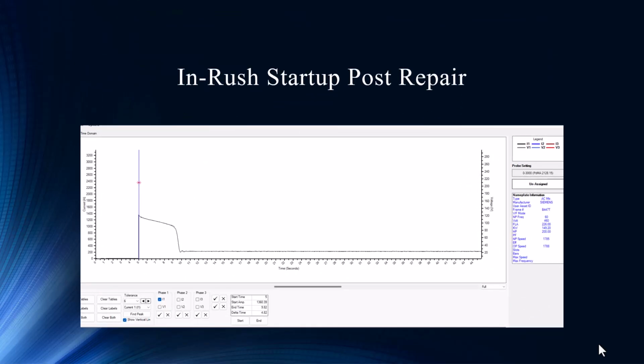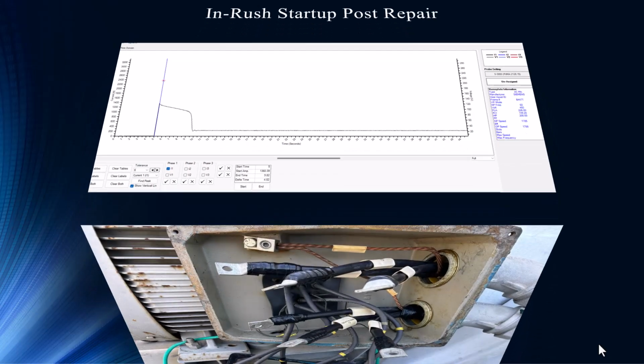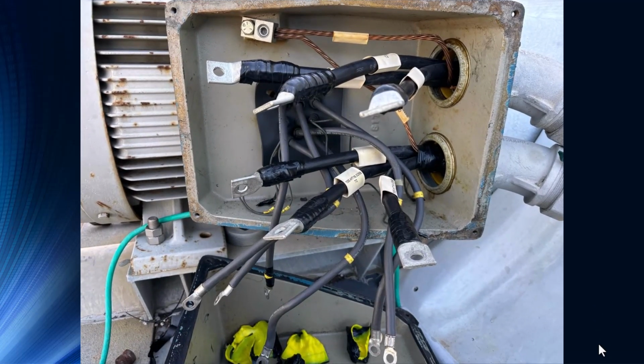Here's the inrush test post repair. Still kind of the same amount of time, but we're not really showing any noise level on the actual. And look at the startup, the lack of differential. They're literally on top of each other, and that's ideal.